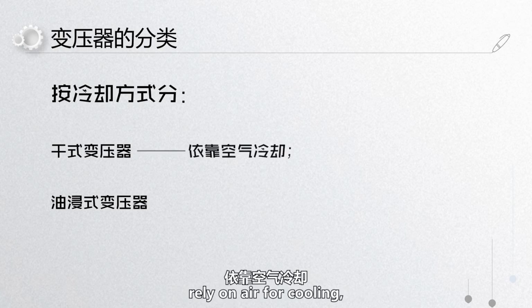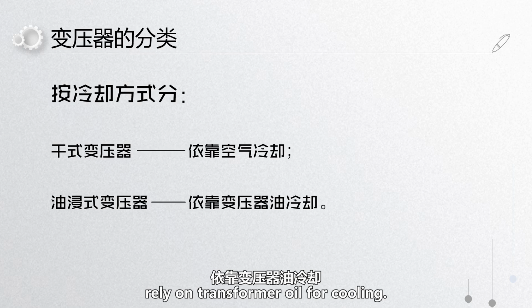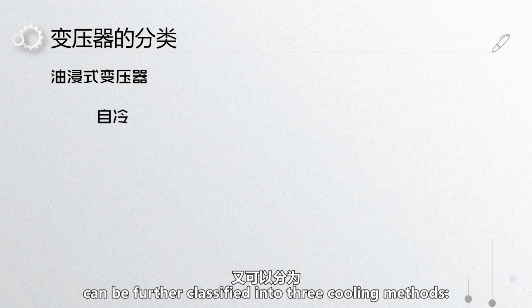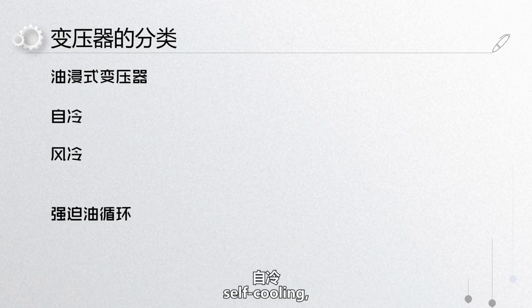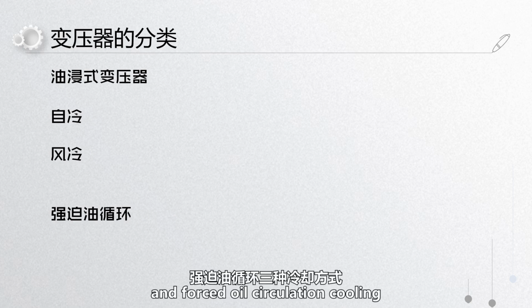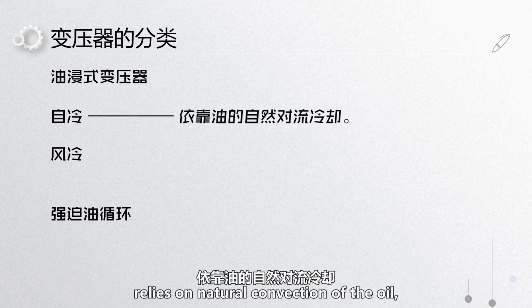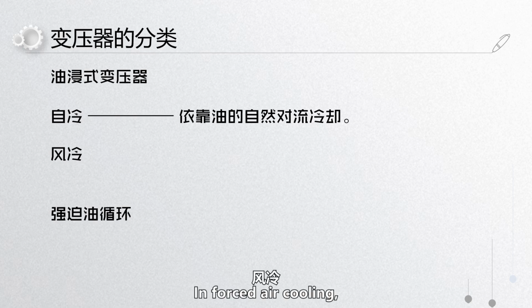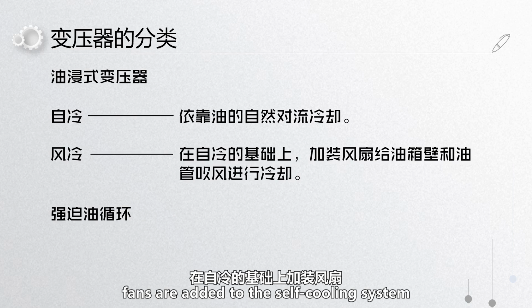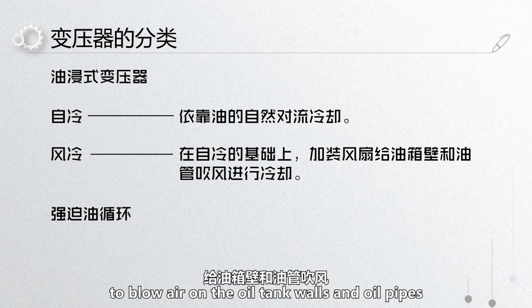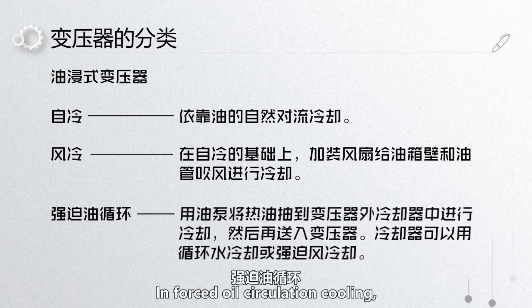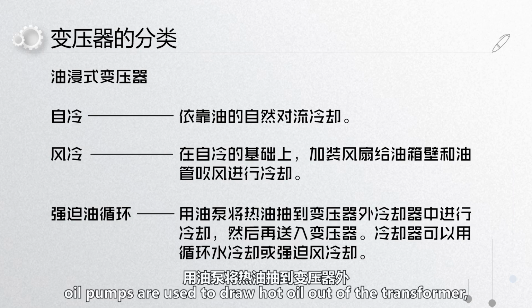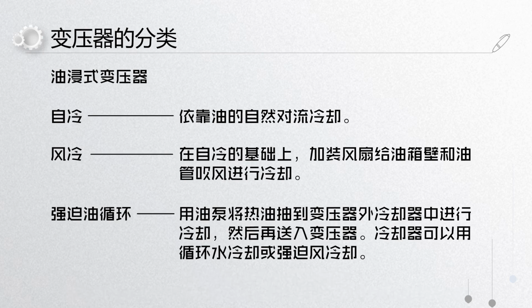Dry-type transformers rely on air for cooling, while oil-immersed transformers rely on transformer oil for cooling. Oil-immersed power transformers can be further classified into three cooling methods: self-cooling, forced air cooling, and forced oil circulation cooling. Self-cooling relies on natural convection of oil. In forced air cooling, fans are added to the self-cooling system to blow air on the oil tank walls and oil pipes for cooling. In forced oil circulation cooling, oil pumps are used to draw hot oil out of the transformer, cool it in a cooler, and then return it to the transformer. The cooler can use circulating water cooling or forced air cooling.